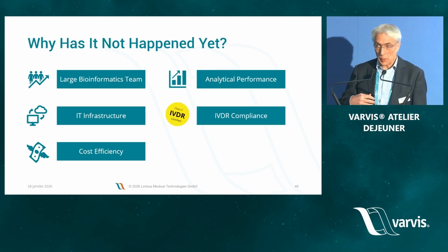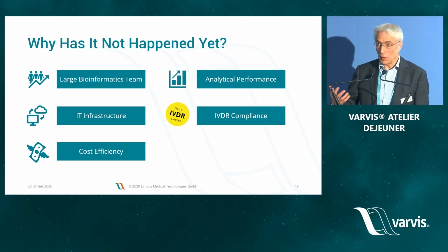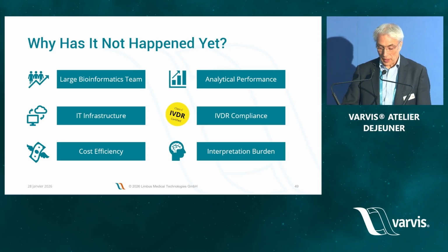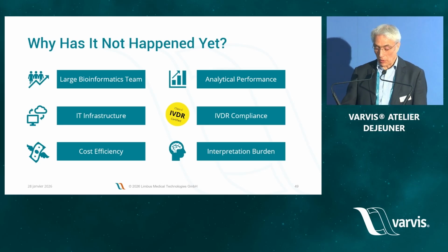And since we are a medical device manufacturer and our device has been approved by a notified body, we can provide you with performance tests so that you can demonstrate also for your own laboratory operations that you're compliant with IVDR.